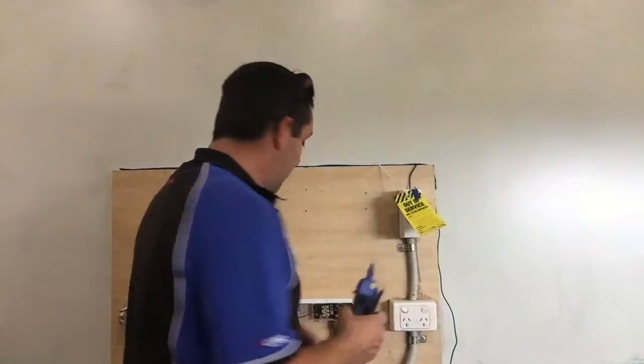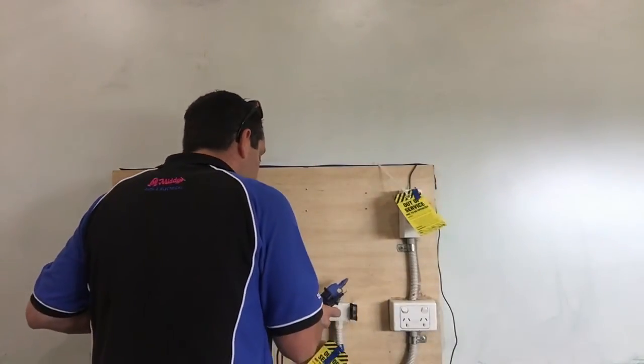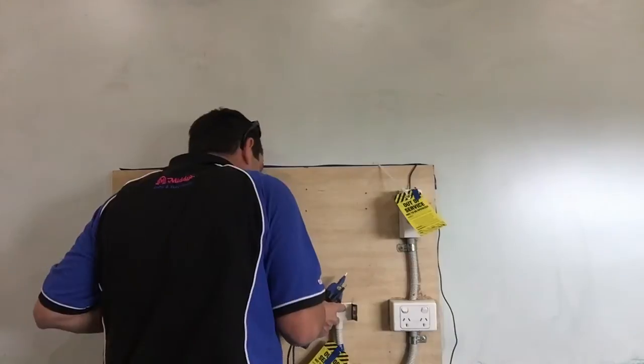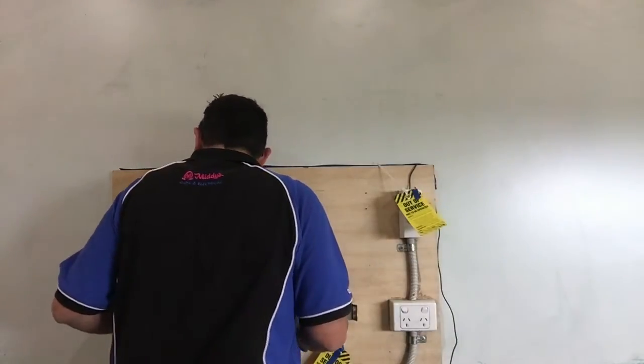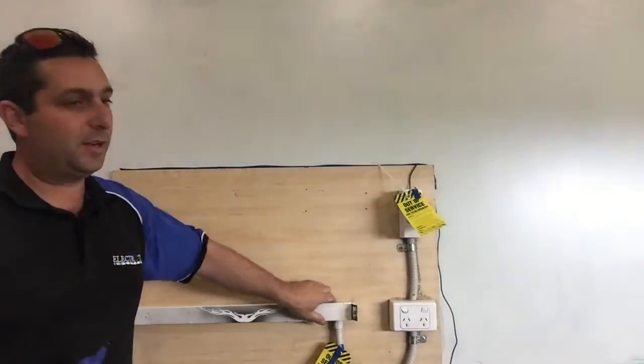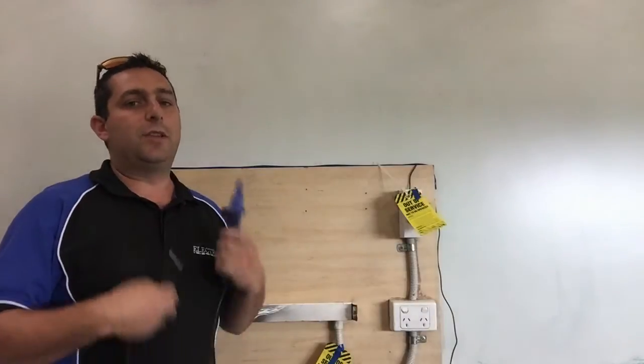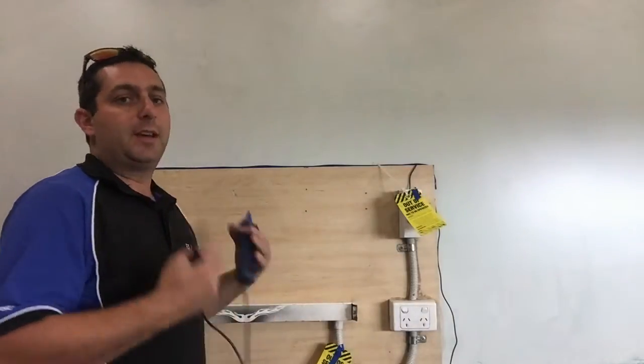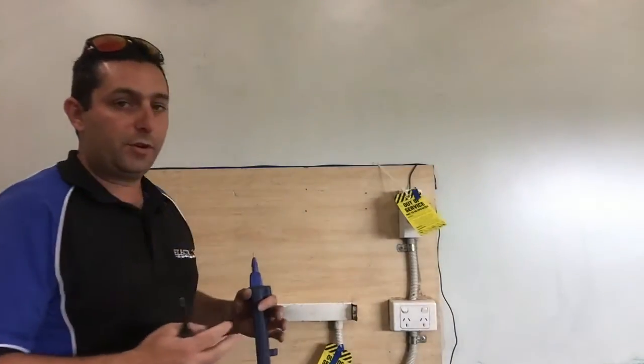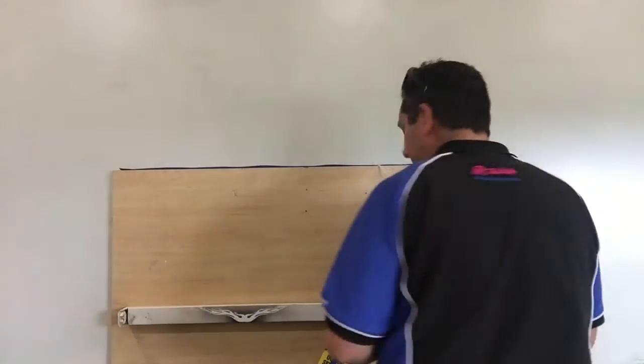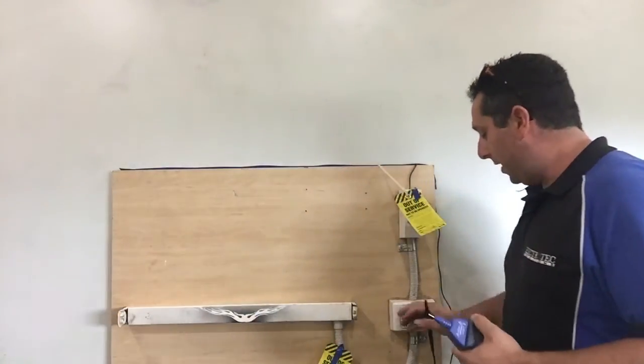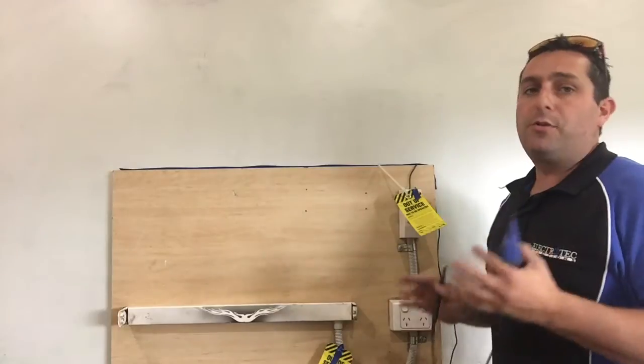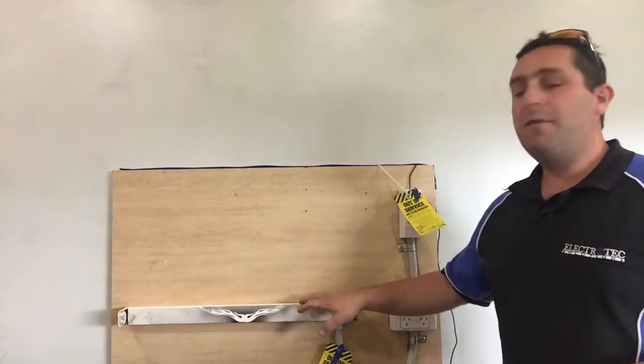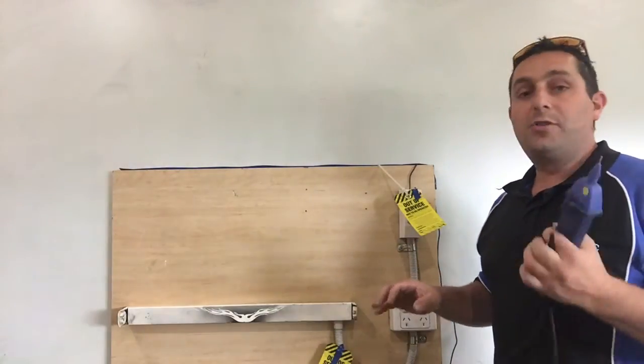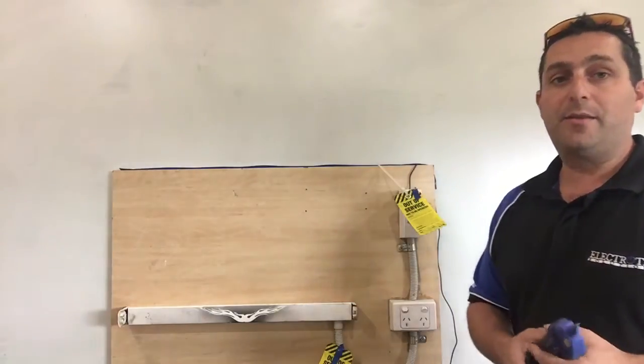this just showed that there is voltage there. I'm not going to take any chances. I'm going to just test my tester and make sure this step isn't necessary, but it's something that I like to do. That every time we test the appliance, get into the habit of putting the cover back on. We're going to go to our known live source. Now, there's a chance that this known live source in the real world could be in a separate room. So every time we go to our known live source, put the cover back on.